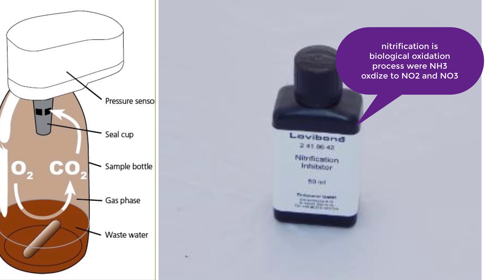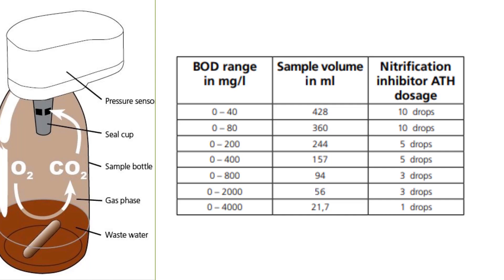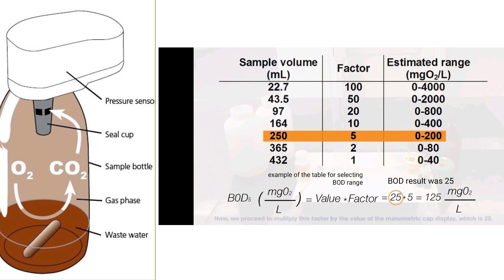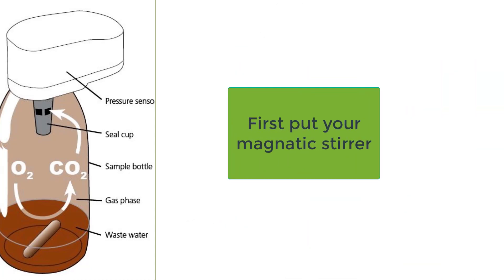This is a BOD table — you find it in your instruction manual. You can select the right volume for your BOD measurement. Also take into consideration there might be a factor that can be used for the calculation of the final BOD result.